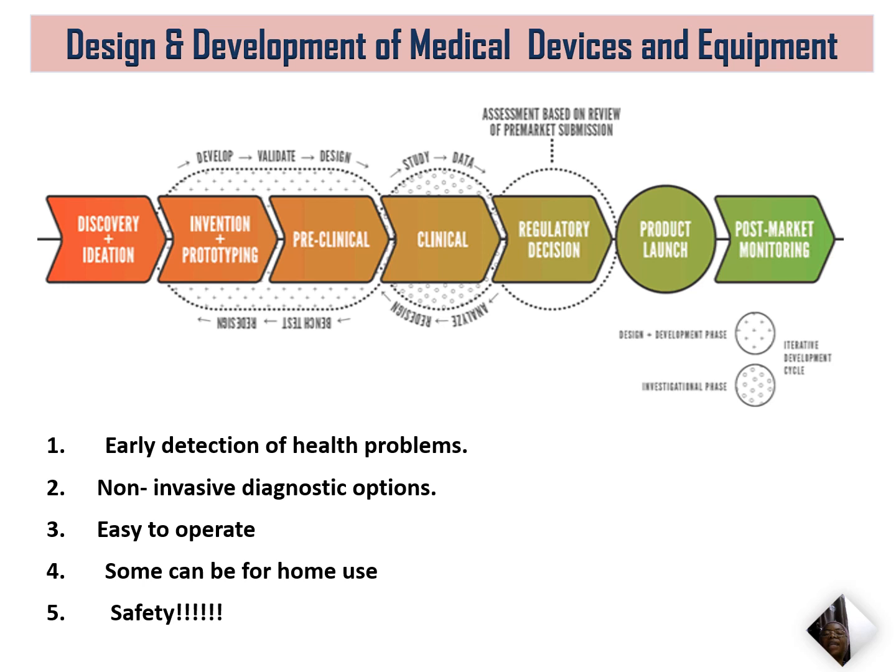Then when it is finally satisfactory, it can be taken to the regulatory decision point where assessment is based on pre-market submission. Then when it is certified, there will be product launch. Then this product launch will lead to post-market monitoring to see the view of customers over the product that is being developed. That is the new medical device that is being developed.